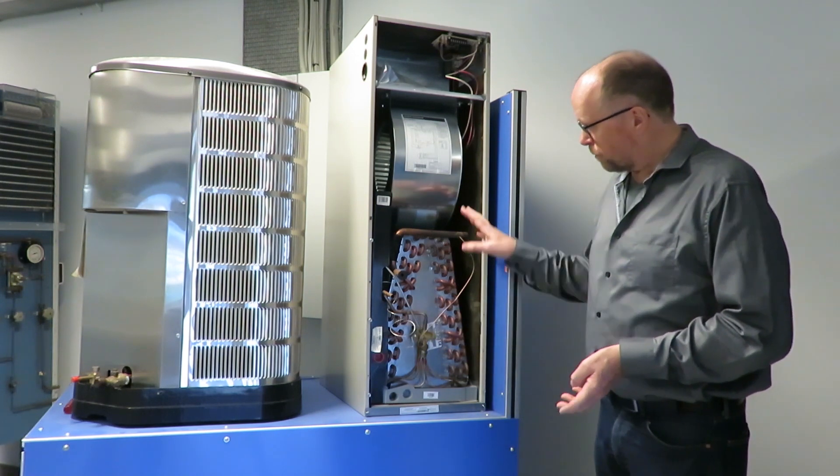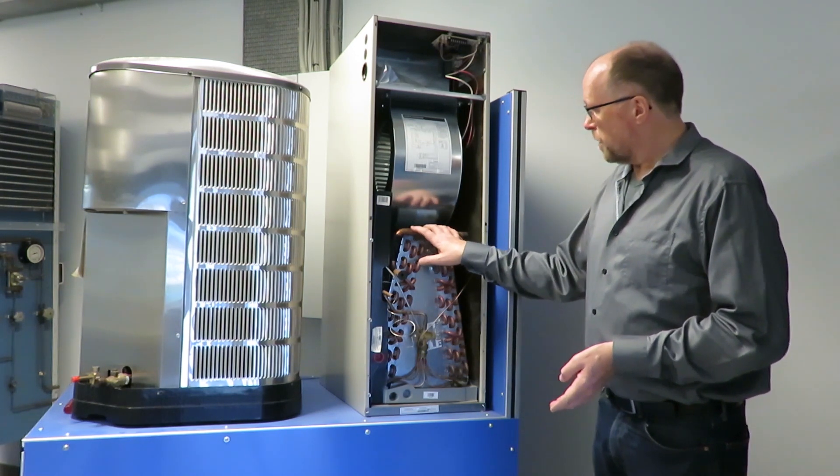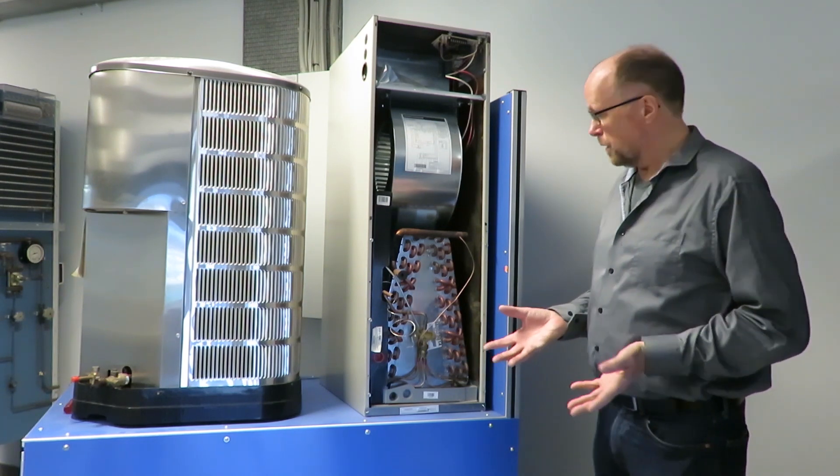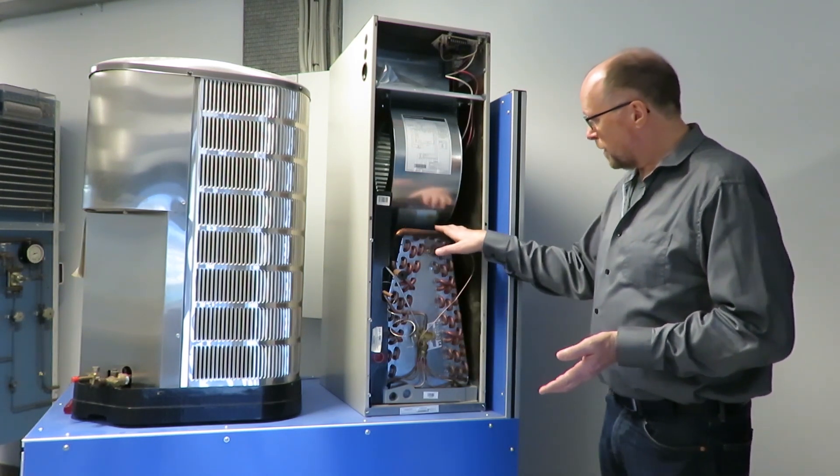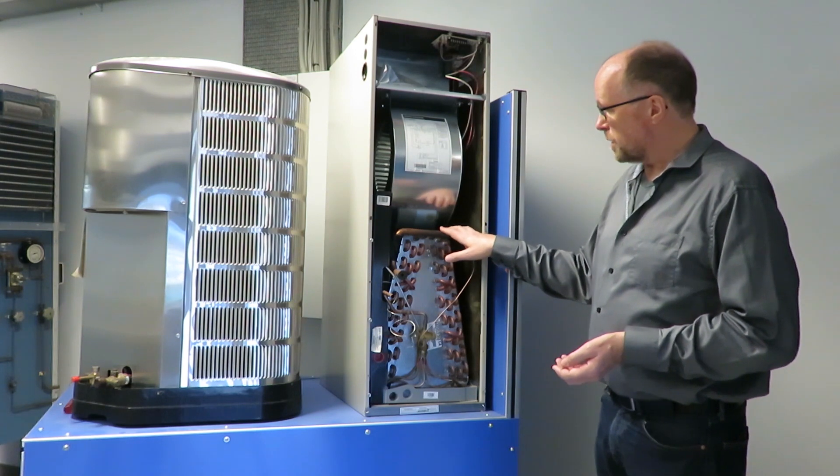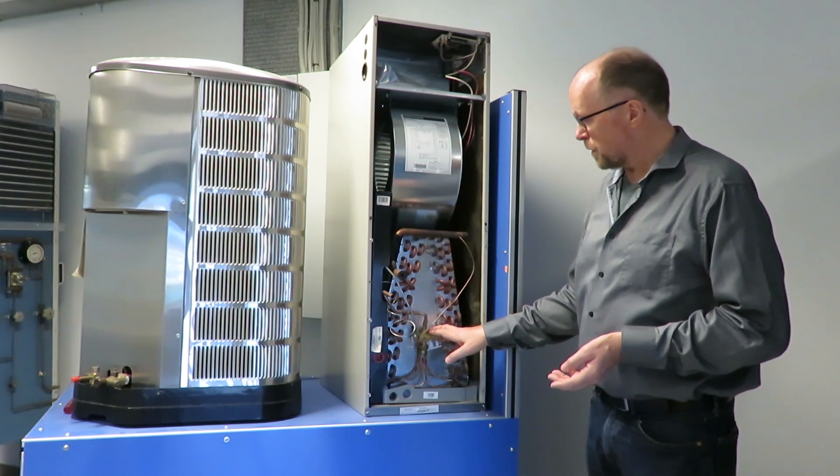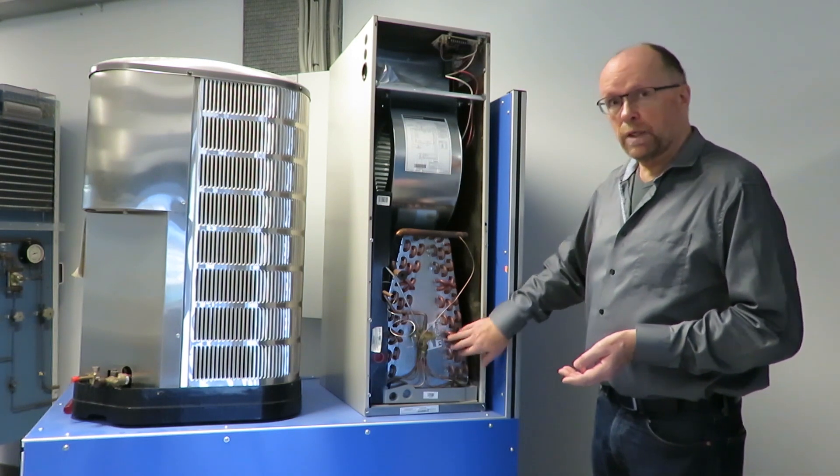It will then, based on how much the load is on the evaporator, how much cooling is needed, and read that by this signal up here, then it will decide how much refrigerant is fed into the evaporator.